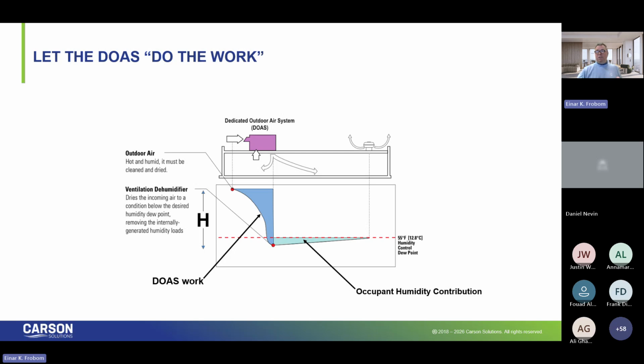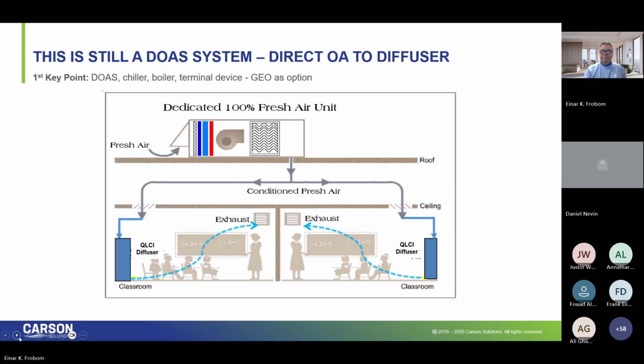And now, if you start at the right peak and dig deep enough in the valley, you will take care of a lot of warts in terms of your DOAS system, in terms of truly decoupling the largest latent loads from the sensible loads. Two things happen. One, you make the system more efficient, and two, you make the environment more comfortable because your terminal device only has to deal with temperature and not temperature and humidity.